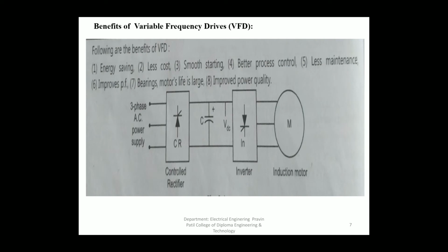This is the block diagram of a VFD. First, the three-phase supply is given to the rectifier, which converts AC into DC. Then the DC output is connected to the inverter. The inverter converts DC into AC, a variable AC, and this variable AC is connected to the stator winding of the motor. Then, benefits of VFD: energy saving, less cost, smooth starting, better process control, less maintenance, improved power factor, longer bearing and motor life, and improved power quality.